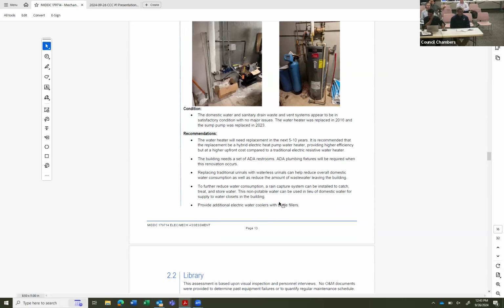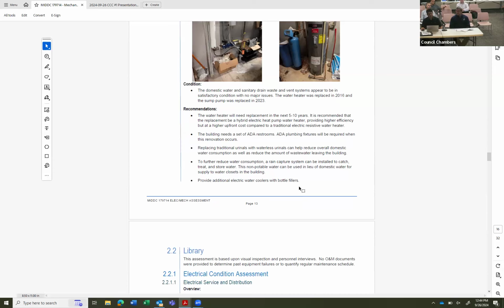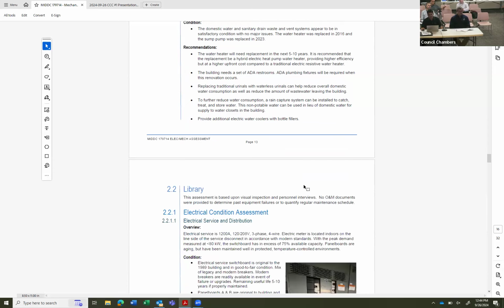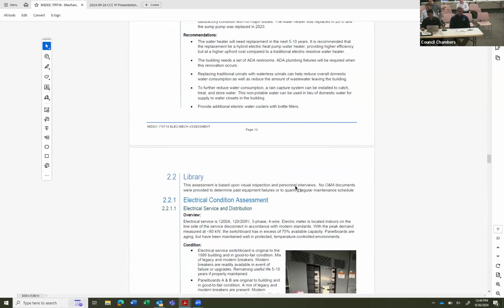And to further reduce water consumption, there is potential for a rain capture system to be installed in the building. We would modify the roof drain and storm drain system, connect it to a tank with chemically treated water, a non-potable system exclusively for water supplied to toilets and urinals and things. Additionally, it's noted that more electric water coolers with bottle fillers are desired throughout the building.